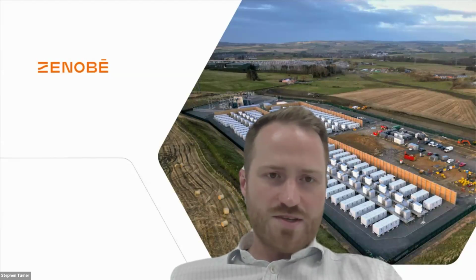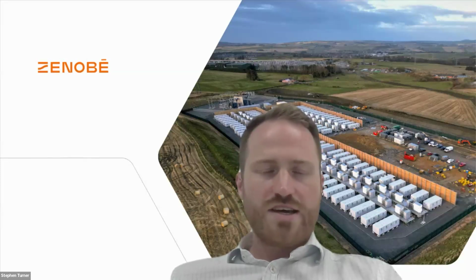The way they've gone about it is by bilaterally contracting with batteries to provide frequency services as well as inertia, working quite a lot with Arena, my former employer, to test out and prove new ways for batteries to provide these services. They've gone with a relatively conservative approach of still using some spinning mass, procuring synchronous condensers to balance the need for SCL and inertia. But they've also been forward-thinking—you can't be spinning these things all the time, it's very expensive if you need that—so they've been quite open to using batteries to provide and replace these services.